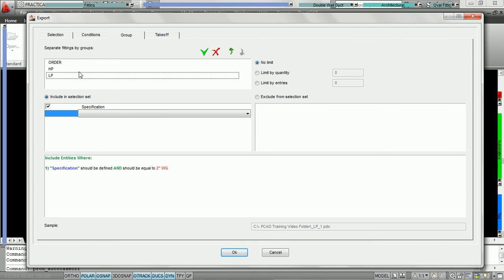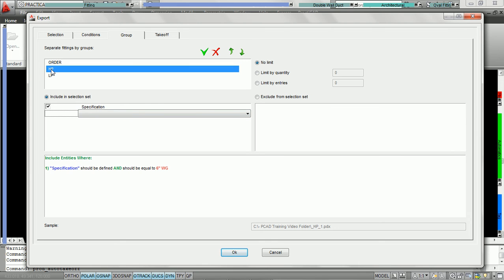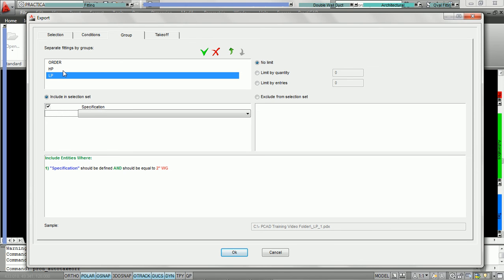Order of conditions is important, and under the tutorials for the PractiCAD layer mechanism we show and explain why you want to order things properly. PractiCAD, when it goes to decide what should go in what group, always starts with the first choice, checks if the conditions meet the selection criteria, and if it does, puts it under order. If it doesn't meet those conditions, it jumps to the next and asks: does my specification equal 6 inch water gauge? If yes, it goes in the high pressure group. If not, it'll jump to the next one and so on. Please watch the tutorials on how to design the PractiCAD layer mechanism and ordering.